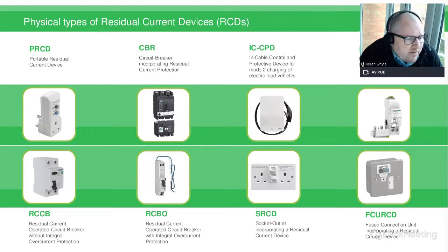Another on the bottom row there, the SRCD, socket outlet incorporating residual current device. Again, I think in the industry, maybe a couple of decades ago, this was possibly the most effective, or maybe the most cost-effective way of providing RCD protection to individual sockets. So instead of obviously having a white plastic socket, you'd have one incorporating the RCD. This obviously got taken over by the RCBO, by having the protection in the main device itself. And then we have the MRCD again on the top row. This is an add-on block to a double pole MCB. Modular device adds flexibility in design. And then the one down the bottom there, the FCU RCD, fused connection unit incorporating residual current device. Again, not seen so much these days.